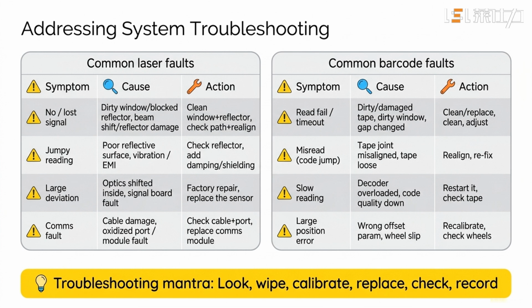The common laser fault is no signal. Usually a dirty window or a blocked reflector. So clean first. For a jumpy reading, check reflector quality and vibration. The most common barcode fault is read failure. Again, clean first. For code jumps, check the tape joints for misalignment. For large position error, recalibrate the parameters first, and only then check whether the travel wheels are slipping. Remember this order, don't jump straight to replacing the sensor.